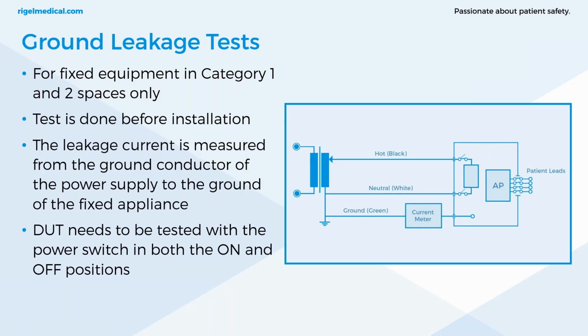So ground leakage tests are not going to be performed as often as your other leakage tests. They're only specified for fixed equipment in category 1 and 2 spaces before you install the equipment. So you're only carrying it out on these specific fixed equipment devices, and you're only doing it before it's installed. So it's not as often you'll be performing these tests. This is just to ensure that all leakage current flows to the measurement circuit of the safety analyzer, and this test is done before those grounds are then connected.